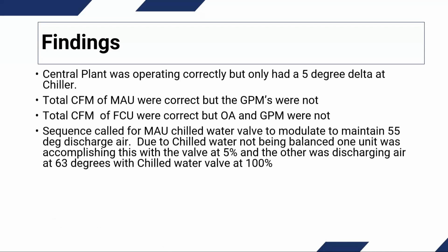The sequence called for the makeup air handling units to modulate the chilled water valve to maintain 55-degree discharge air. That's what they were doing, but since the water was not balanced, we noticed that we had one unit that was able to deliver the 55-degree air with the chilled water valve just cracked open at 5%. We had another one that was delivering 63-degree air with the chilled water valve at 100%. Again, indicating what we already knew, that the water had not been balanced or needed to be balanced.